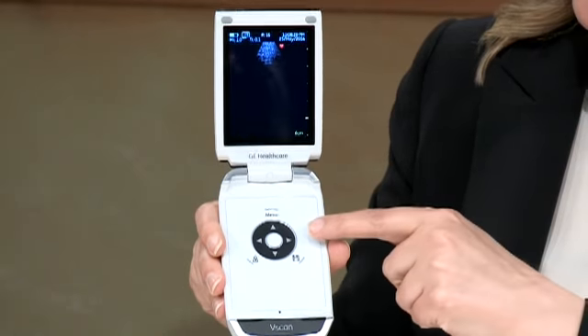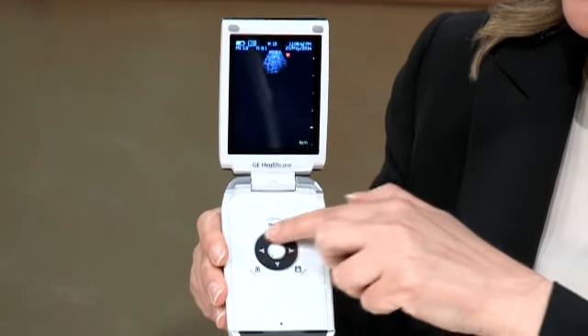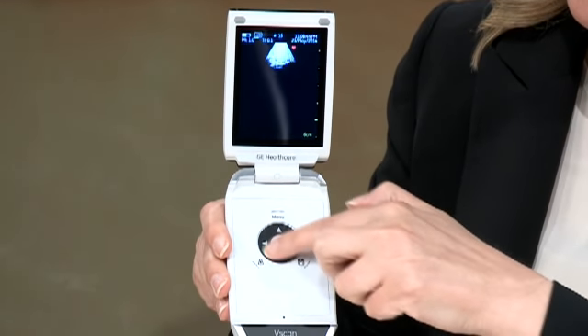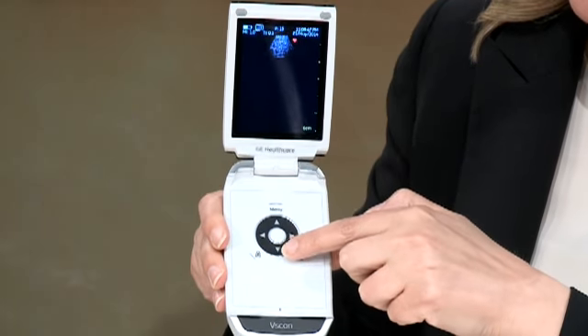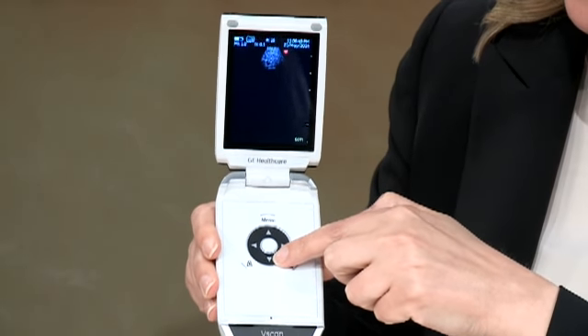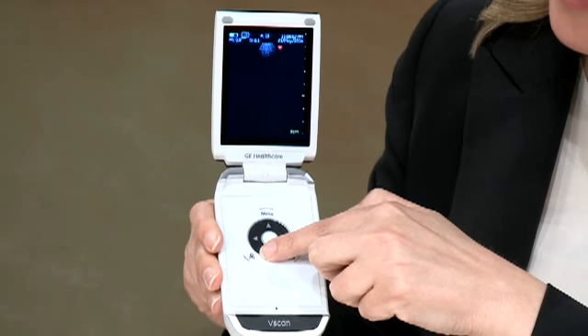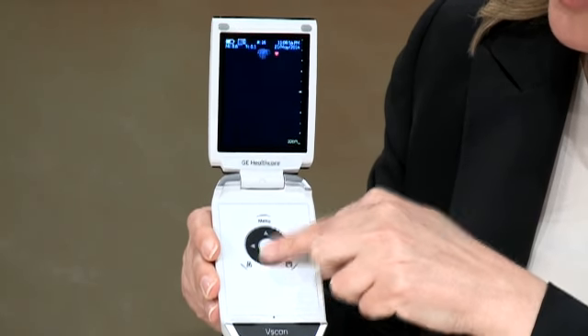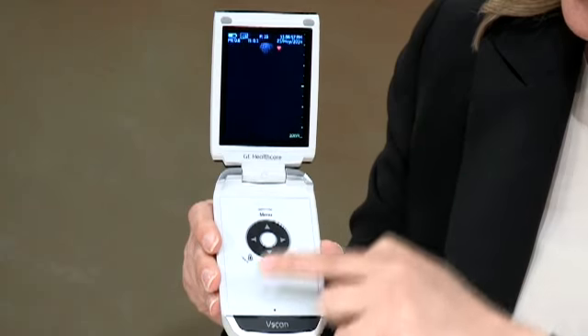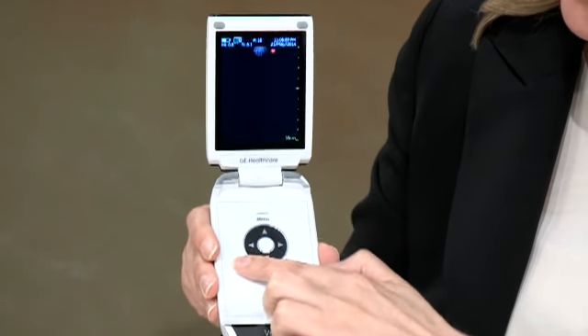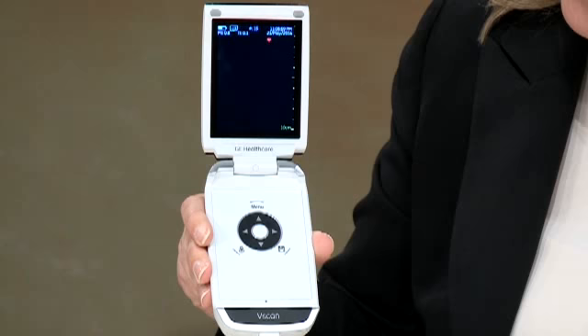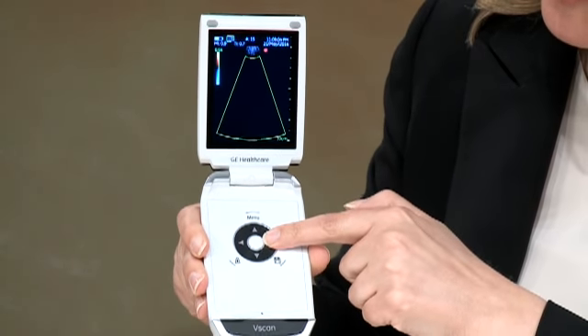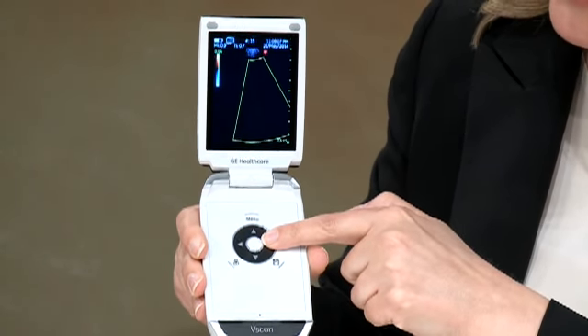Let's take a look at the dual transducer's general user interface. The Vscan with Dual Probe automatically boots to black and white imaging. Here, the black wheel in a clockwise motion increases the gain, counterclockwise decreases the gain. The up and down arrows support the depth mode. So by pressing the depth arrow, you can see the adjustment displayed on the screen. Over here we have color flow mode. Pressing color activates color, and then the arrows will enable you to pan the color region of interest as necessary.